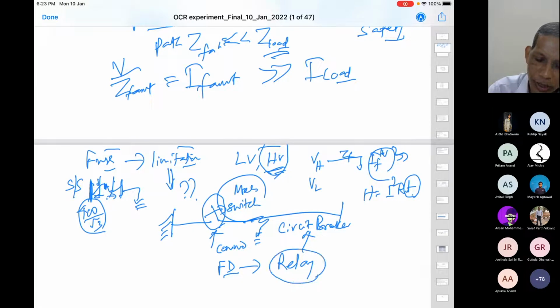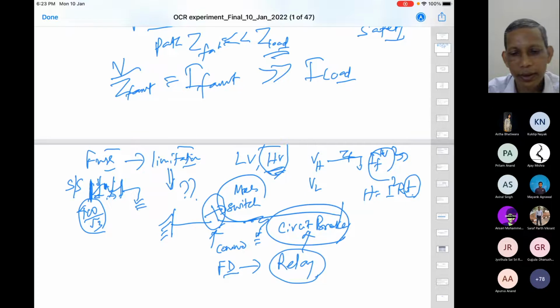So we essentially require the relay and the circuit breaker in the system. The relay is the fault detector. Earlier we had electromagnetic relays, then with the evolution of the transistor, static relays came into the picture, and finally we converged to numerical digital relays, which are what most of the grid has today.